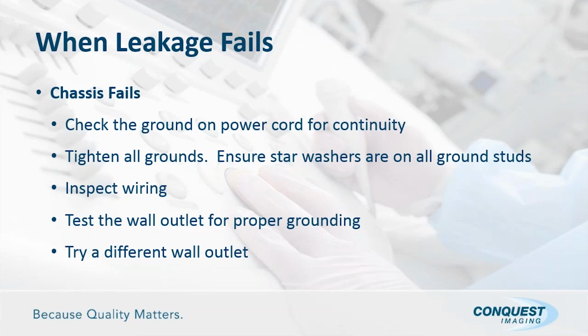Tighten all grounds. Different systems have it grounded differently, but they say to ensure you're using star washers on all grounded studs so that you have a good connection. Inspect wiring, again, not only on the power cord, but on peripheral power cords, on cabling going to, say, a DVR. Make sure you inspect all the wiring, that it's accurate and tight and that there's no damage to it. And one of the things we mentioned earlier is to test the wall outlet for proper grounding.